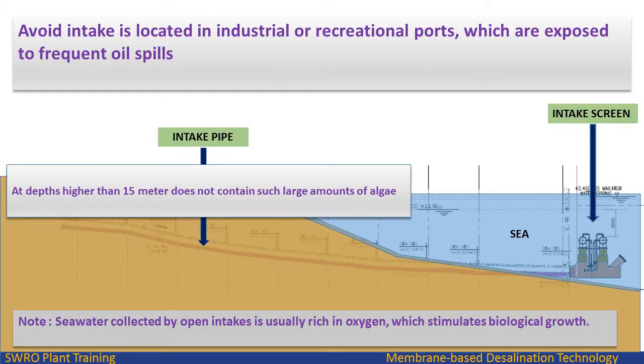The following points should be considered when installing an intake screen: Avoid placing intake in industrial or recreational ports, which are exposed to frequent oil spills. Intake at depths greater than 15 meters does not contain such large amounts of algae.